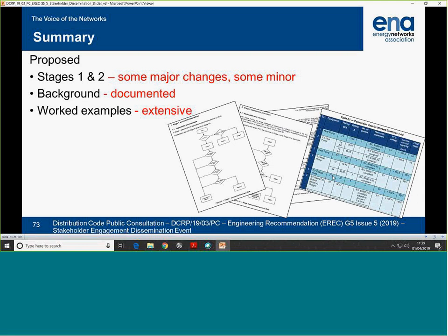Is there any intention to roll this out, so that the DNO comes back and says, okay, we'll put a connection application in and we'll feed back data? We can't do anything until you put a connection application in, which I understand. But at some points the fault level may be really poor and it may be the wrong place to connect to the main. Is there any thought of rolling out data on what the fault level is?